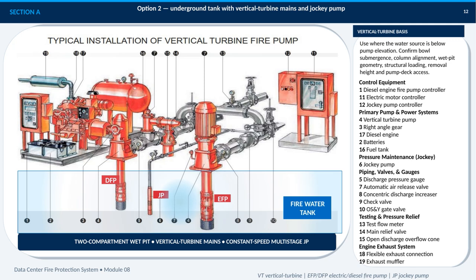Adequate bowl submergence, proper column alignment, sufficient wet pit geometry, structural loading, removal height, and clear access to the pump deck. The supporting equipment includes the electric and diesel controllers, diesel engine, right-angle gear, batteries, fuel tank, pressure gauges, automatic air release, check and OS&Y gate valves, and a concentric discharge increaser. Testing and pressure relief are handled through the flow meter, main relief valve, and open discharge overflow cone. Finally, the diesel package includes the flexible exhaust connection and muffler, while the relief return remains independent.